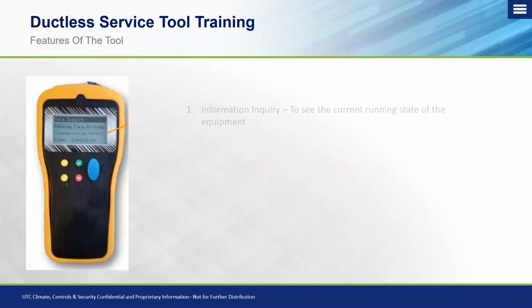So, getting into features of the tool. The first part of this tool is going to be your information inquiry. This is to see the current running state of the equipment. This is sensors such as T1, T2, T2B, T3, T4, and T5, which, if you paid attention to the last part that we were talking about as far as the advanced features and control, T1 and T2 are our indoor coil temperature sensor and our return air temperature sensor. T3, T4, and T5 are outdoor coil temperature sensor, outdoor ambient temperature sensor, and also our compressor discharge temperature protection sensor. So you can see all of that information.